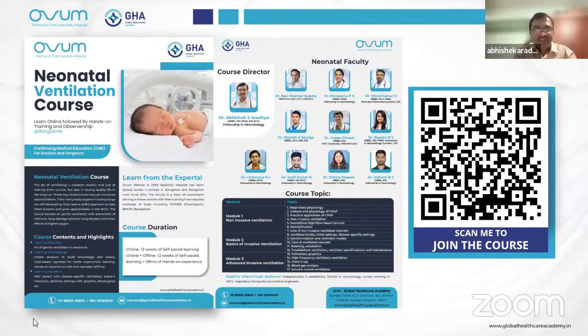We'll close the question and answer session there. I think most of the questions are repeating. They're asking, if you're using CPAP and want to give a PEEP of 4, is it the inside 4 or the outside 4? What number should be visible in a bubble CPAP is their question. Whatever is seen at the tip of the jar is the level, and you can cross-check it by looking at the water level. From the water column, it should be 4 centimeters down. You can measure from the water column whether 4 centimeters is down or not. Whatever is visible at the tip is the actual value, because that displays how much of the tube is inside water in the bubble jar.